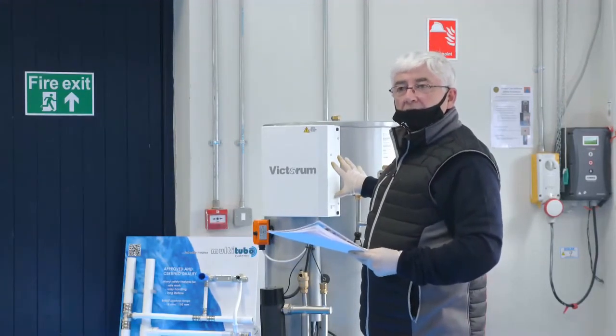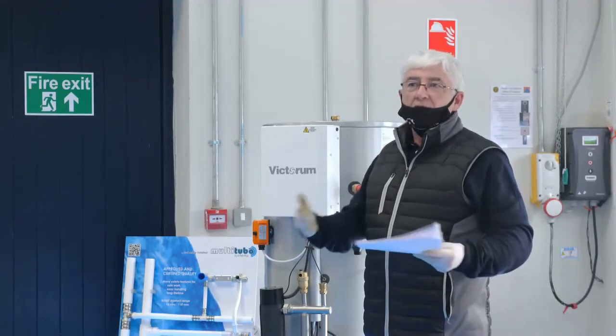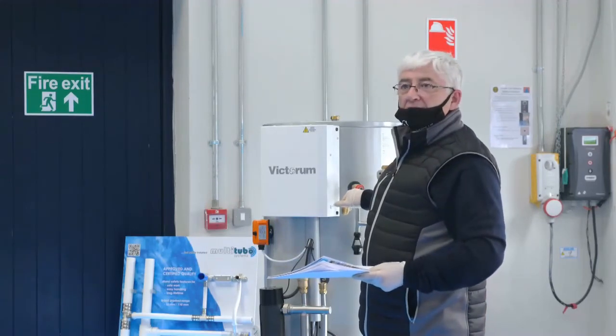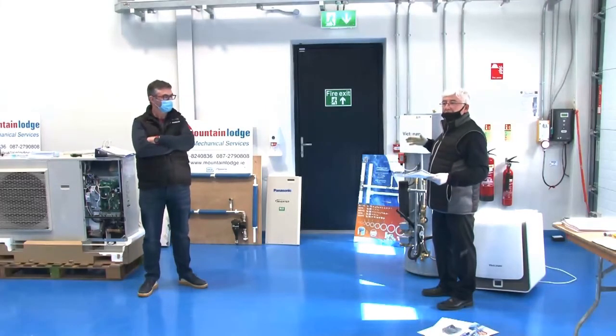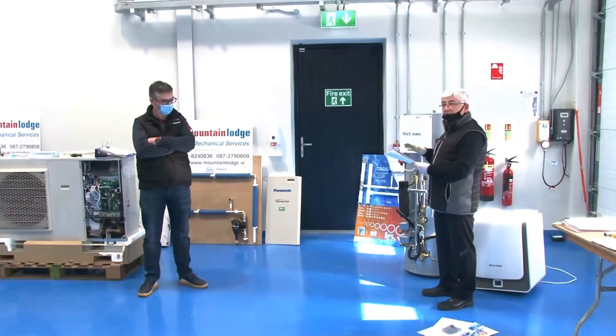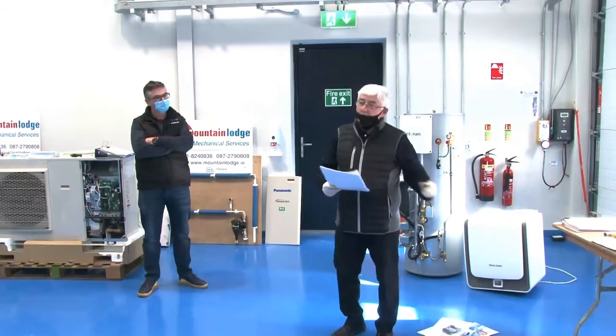and your plant and equipment? So imagine using a system that could withstand 3 bar at 95 degrees, and you have a pressure relief valve at 6 bar at 95. Then your service conditions are lower than the safety conditions. So you have to watch for things like that. There are markings on all pipes.